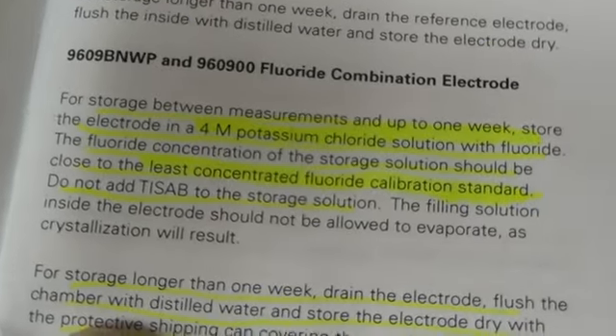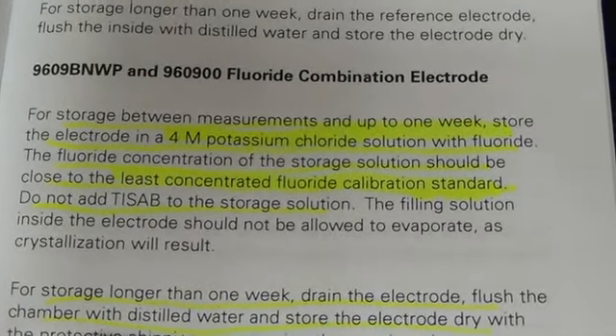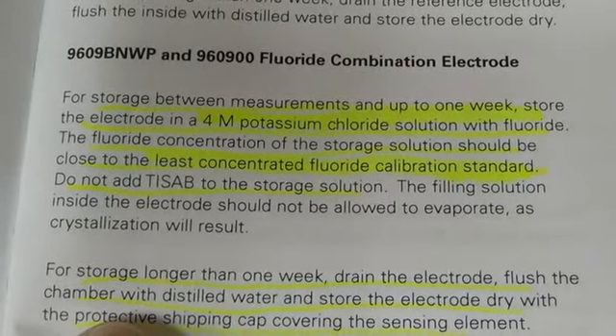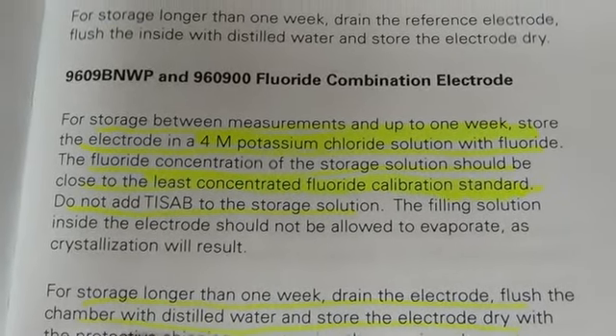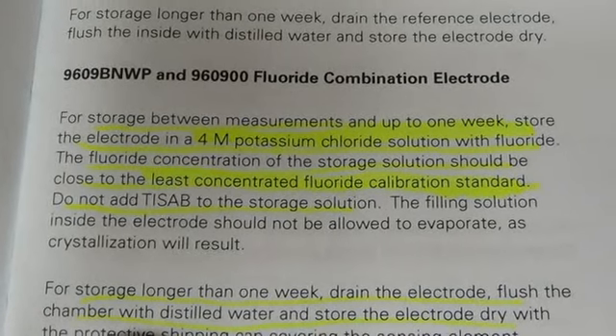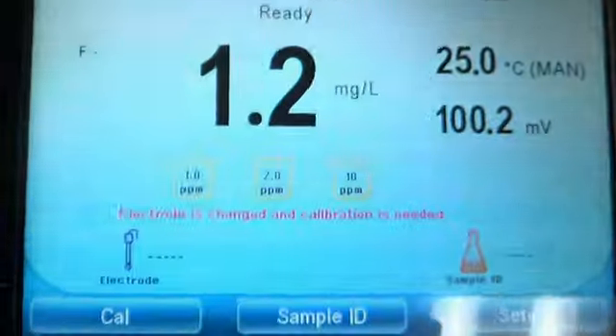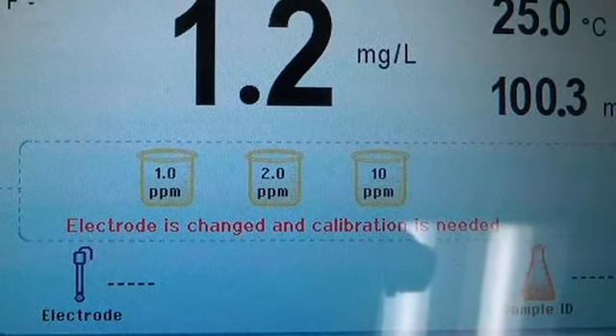After your probe is filled, you need to soak it. The directions say it must be in a 4M potassium chloride solution with fluoride. The amount of fluoride in there should be at the least concentrated fluoride calibration standard. Right now this meter is set up to run at 1 ppm as our lowest standard, so we should make this 1 ppm. It should be prepared for you before you come in.